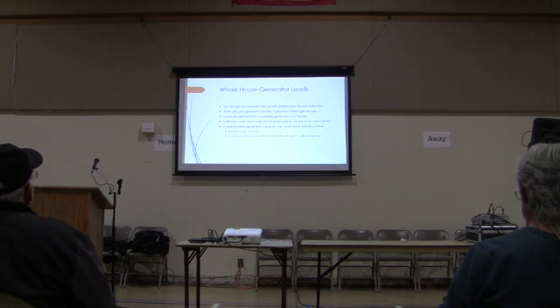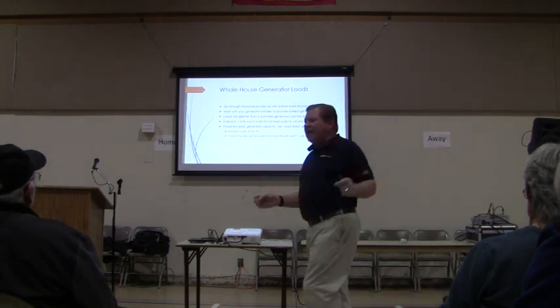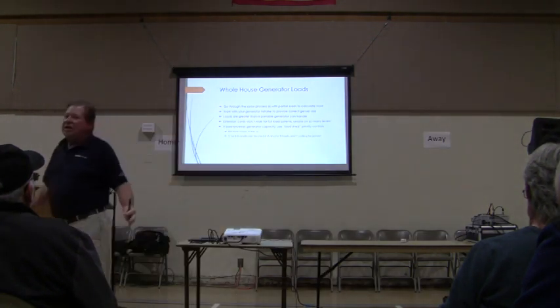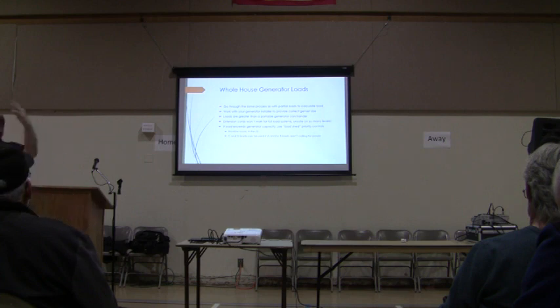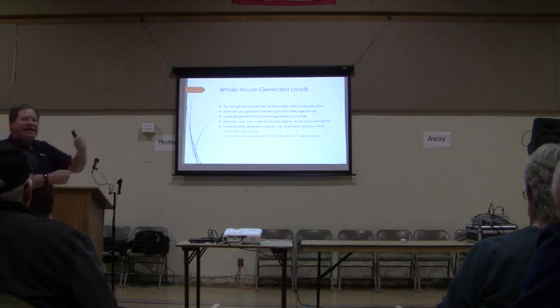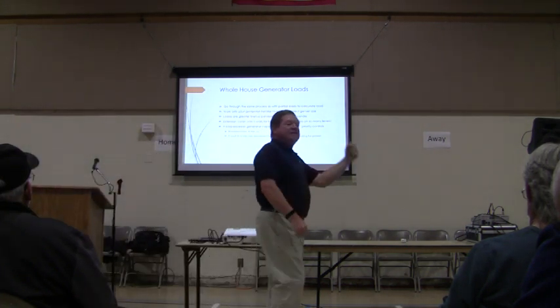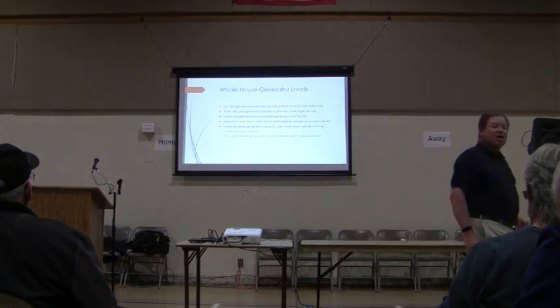With the whole house generator load, you go through and pick everything you have, and it'll give you a good idea of what you need. Now if you discover you need a 40 kW generator because everything's electric in your house, you can go to a priority load shed device where you prioritize the loads, and it will energize circuits if the power is available for those loads.